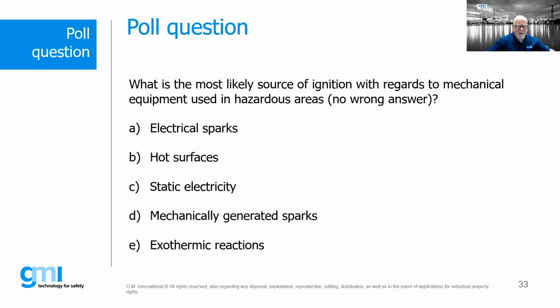The IEC standards are published, and it's up to - they carry no legal weight, if you will, unless adopted verbatim by some governmental entity. So what's really important to note is to look at specifically what carries the most weight, which is that country's wiring regulations. In the United States, we follow the National Electric Code. But ultimately it falls down to the authority who has jurisdiction - we call that the AHJ. And depending on where you are in the world, in the United States we have multiple AHJs.